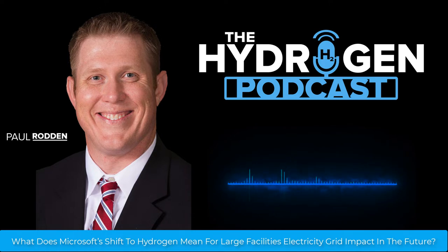When a power outage occurs, batteries in the UPS can keep the data center running for several minutes, which is more than sufficient to ramp up a diesel or hydrogen generator. Once ramped up, backup generators, in theory, can keep the data center running indefinitely, as long as they have a fuel supply. Starting that June day in Latham, and for the next several weeks, Spink's team ran the 3-megawatt hydrogen fuel cell system through the tests Microsoft uses to qualify diesel generators, to prove it could function reliably, including simulated power outages and hours-long runs.